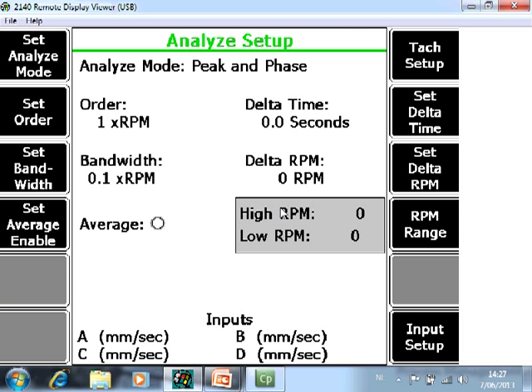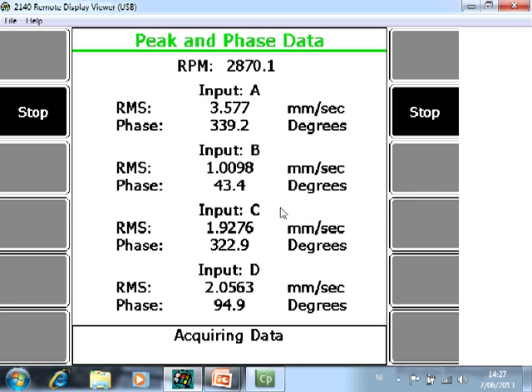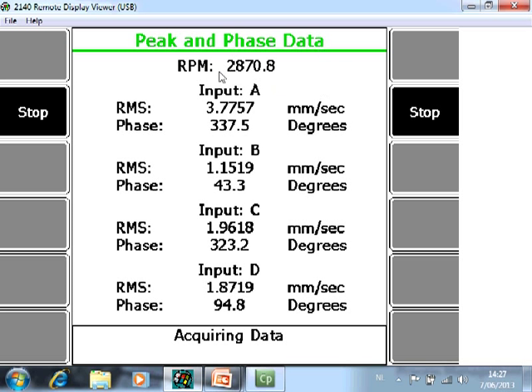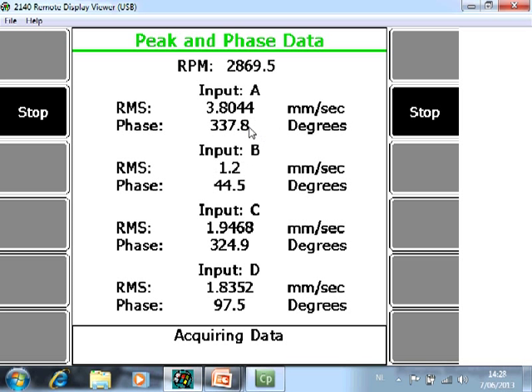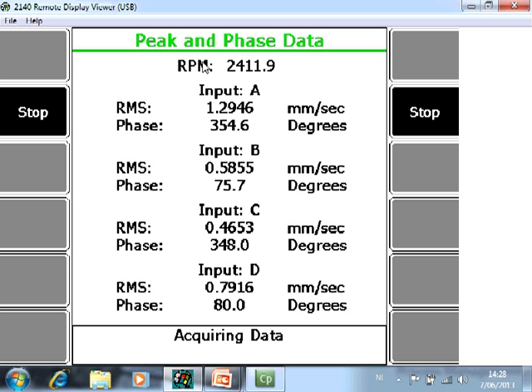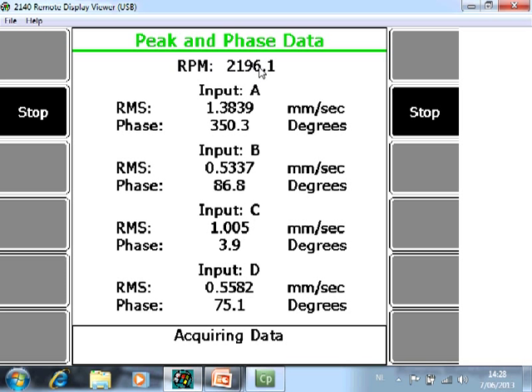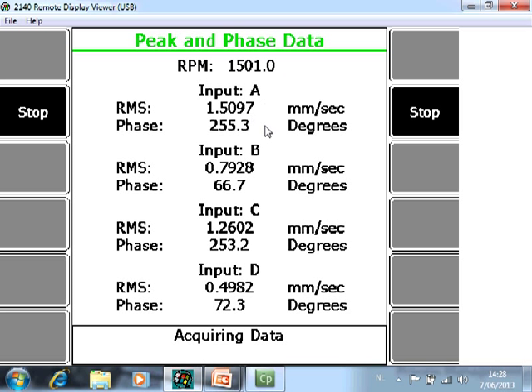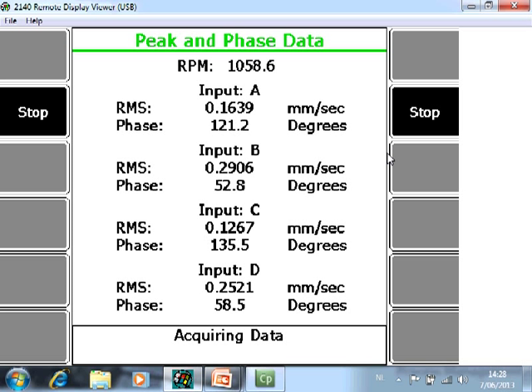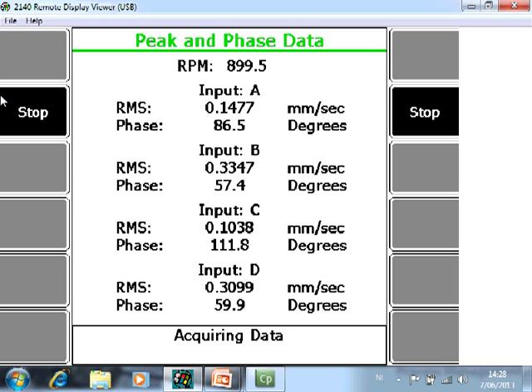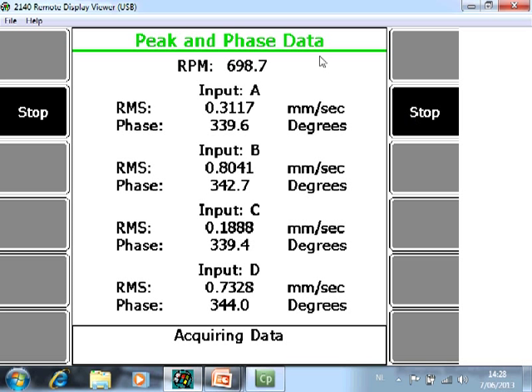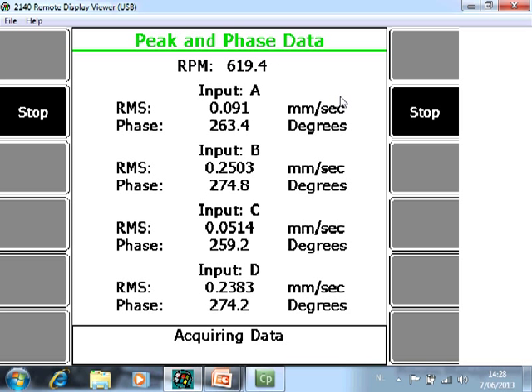So I will now start data collection. This is the screen that you see during data collection. You see the speed at this moment at the top and amplitude and phase measurements for every channel. When you stop the machine, of course the machine will go slowly down. You see the speed at any moment in time here and amplitude and phase for all the channels. You can stop data collection by clicking F2 or F8 at any moment in time. I will stop the collection when the speed is around 600 RPM. So I will stop now.